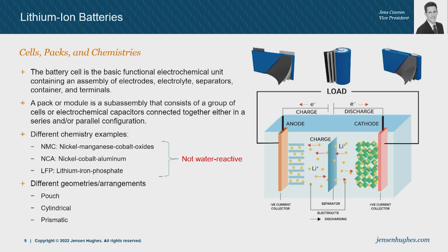Most popular in automotive are nickel manganese cobalt, that's an LG thing, or NCA, likewise LFP, lithium iron phosphate. What's important to note, since this is also a fire safety talk, is that in these cells there's no lithium metal, so it's not water reactive. So if we're dealing with battery fires, it's okay to put water on it. Otherwise, we're always thinking, oh, lithium, don't put water on it. That was the case for a primary lithium battery, but not for a secondary lithium-ion battery.